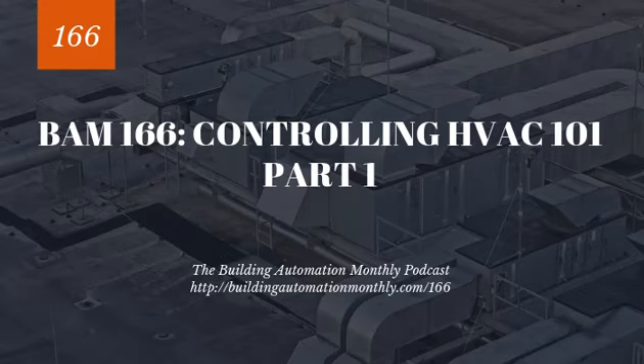And this is where you can run into some issues when you're troubleshooting, is you're not taking into account not only the airflow, but also the pressurization aspects of the airflow. So for example, if you have a hallway that is very poorly conditioned and has poor temperature control, and it's really overpressurized, and it is pushing into spaces, and these spaces maybe are underpressurized, you may actually be having issues with temperature, not because of the control of necessarily temperature in the space, but because of all this unconditioned hallway air or less conditioned hallway air that is leaking into these spaces.